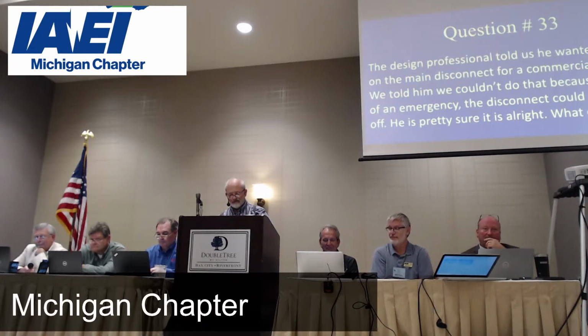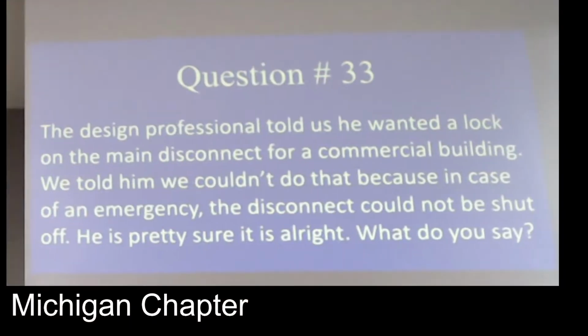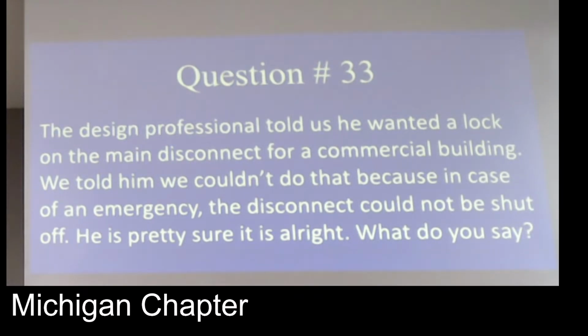Okay, Joe. The design professional told us he wanted to lock the main disconnect for a commercial building. We told him we couldn't do that because in case of an emergency, the disconnect could not be shut off. He is pretty sure it is all right. What do you say? I'm going to agree with the design professional on this one. There's no prohibition about locking an overcurrent device, a main disconnect. Happens all the time, in fact.